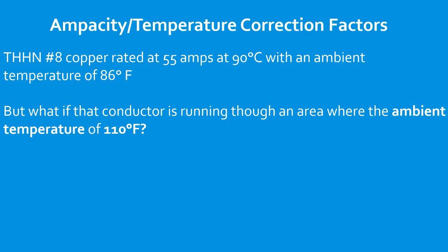What if that conductor is running through an area where the ambient temperature is 110°F? The codebook has made provisions and given us multipliers — think of them just like demand factors. Before we get started, if you're in the 2017 codebook, go to page 148 and cross off Table 310.15(B)(2)(b) — the larger upper table on that page. If you're in the 2020, go to page 159 and cross off Table 310.15(B)(2) — the lower table on that page. That table looks identical to the one we need, but we never use it.